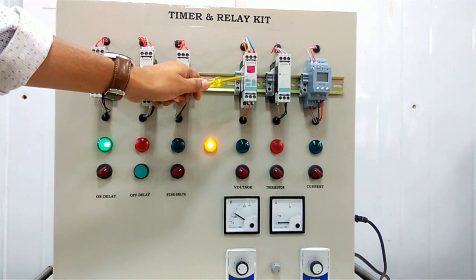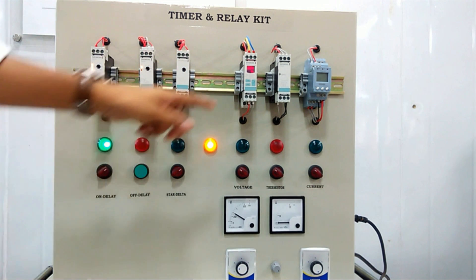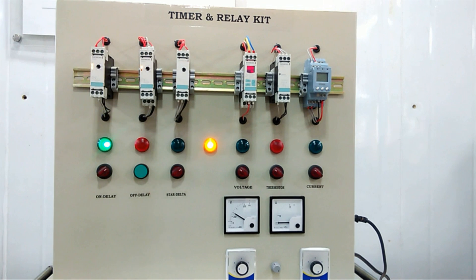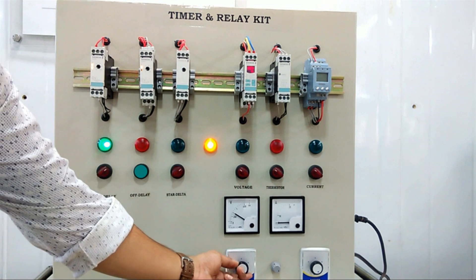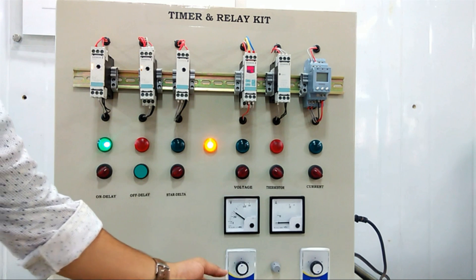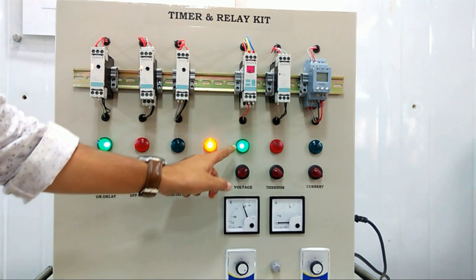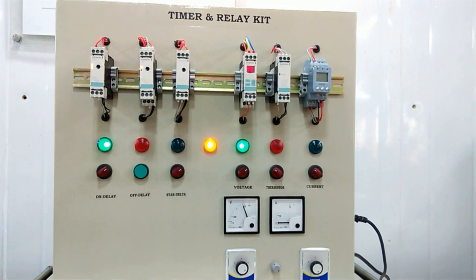Next is the voltage monitoring relay. We have already set the voltage threshold. I will enable it and increase the voltage from this pot. You can see that when the voltage crosses the limit, the relay trips and we get an indication.